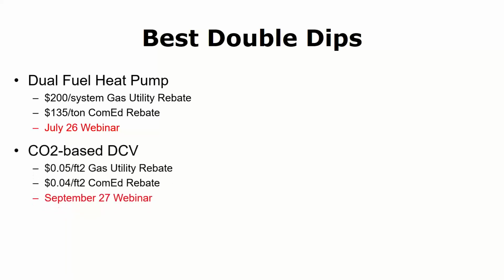Demand control ventilation with CO2 sensors, as I just mentioned, gets you 5 cents per square foot from the gas utility side and 4 cents from ComEd, 9 cents total. Multiply the 9 cents by the square footage covered by that system, and that's a decent amount of free money - typically more than the sensor itself costs. We have a webinar on the exact technology and how it works on September 27th.